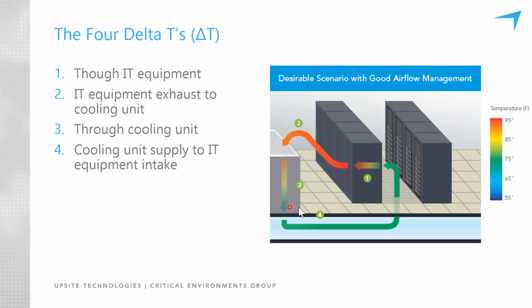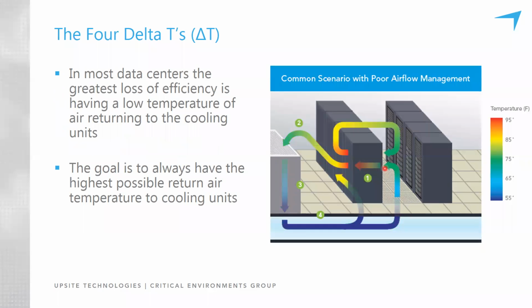And that's the change in temperature of the air from the time it leaves the IT equipment before it returns to a cooling unit, and the change in temperature of the air from the time it leaves a cooling unit before it gets to its warmest inlet temperature to IT equipment. This image shows an ideal scenario. We're not seeing much temperature change for 4 and 2, but in this image of typical conditions, we're seeing a lot of change. These temperatures, the colors are accurate to the color scale on the right. Very commonly, air is supplied from cooling units around 60 degrees, and yet the warmest intake to IT equipment is somewhere around 75 or 80. So why did the air warm up 20 or 30 degrees from the time it left a cooling unit?